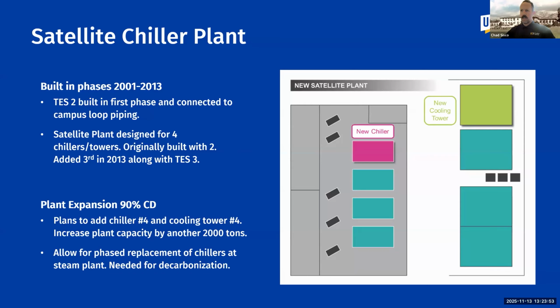And we're also taking the time to retro-commission TES-3 because it's never really been able to operate independently in discharge mode during the peak demand. It just can't flow enough GPM to meet the peak by itself like the other 2 can. So what I did find is that value engineering at the time reduced the internal diffuser system to that point.